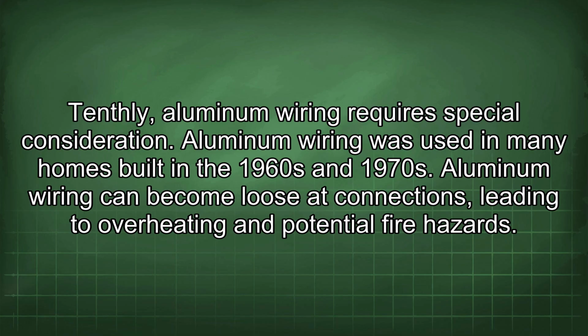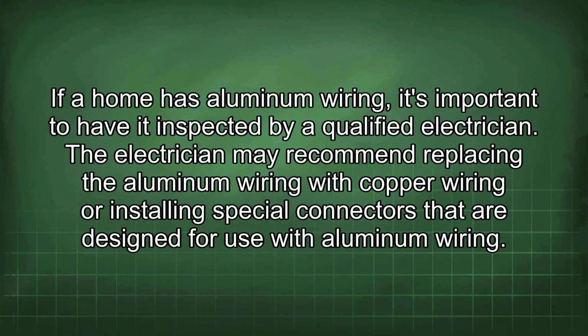Tenthly, aluminum wiring requires special consideration. Aluminum wiring was used in many homes built in the 1960s and 1970s. Aluminum wiring can become loose at connections, leading to overheating and potential fire hazards. If a home has aluminum wiring, it's important to have it inspected by a qualified electrician. The electrician may recommend replacing the aluminum wiring with copper wiring or installing special connectors that are designed for use with aluminum wiring.